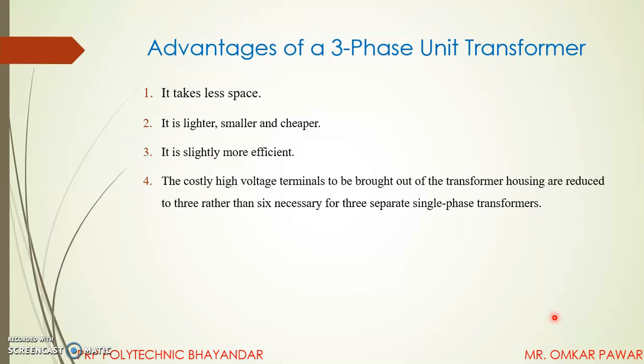The advantages of a three-phase unit transformer. First advantage is it takes less space compared to three single-phase units of transformer. Second, it is lighter, smaller and cheaper. Third, it is slightly more efficient compared to three single units of transformer. And the costly high voltage terminals to be brought out of the transformer housing are reduced to 3 rather than the 6 necessary for three separate single-phase transformers.